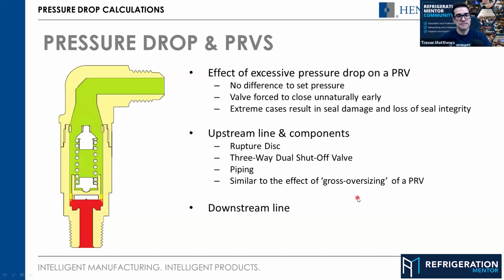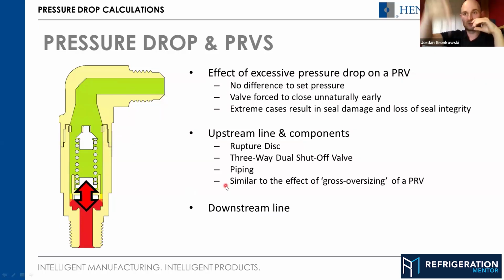Okay. Yep. So the downstream line is the opposite. You've still got your high pressure at the inlet, but if you have a long, excessively narrow diameter pipe on here, the pressure doesn't drop enough through the PRV because you have all this built-up back pressure behind it. And it's the same thing. In fact, from this point of view, it's getting forced closed by the excessive pressure in the outlet. As soon as it closes, that flow stops. As soon as the flow through here stops, your back pressure disappears because there's no flow, and the pressure is back to atmospheric pressure. So the valve will open again. But as soon as it opens, the flow starts, and you're into the same scenario. So it's the same thing, but on the downstream side.